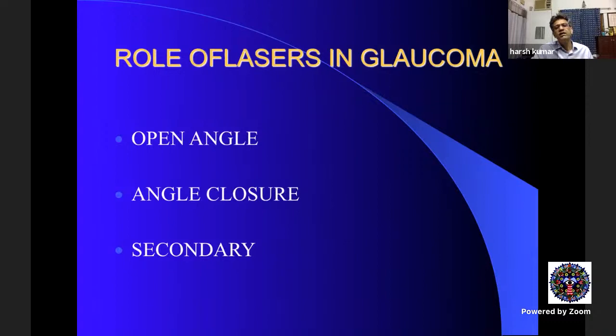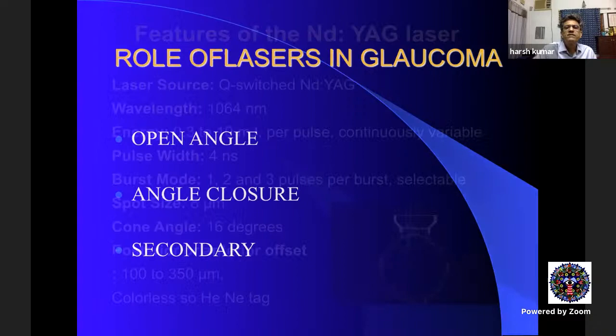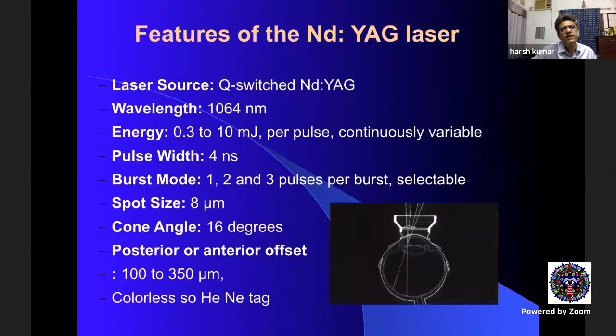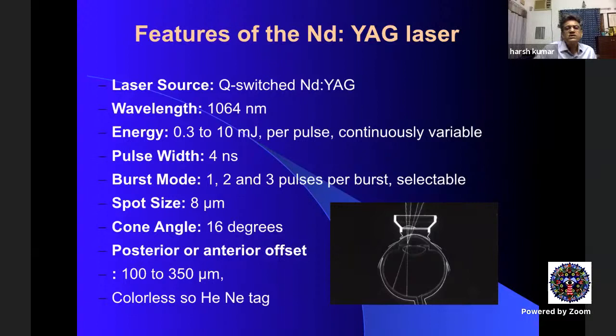Lasers are used in open-angle, angle-closure, and secondary glaucoma. The Q-switched ND:YAG operates at 1064 nanometers. A 532 nm Q-switched frequency-doubled laser is a coagulative laser — so 1064 nm is photo-disruptive and 532 nm is coagulative. The energy used is 0.3 to 10 millijoules per pulse, with multiple pulses available in burst mode.